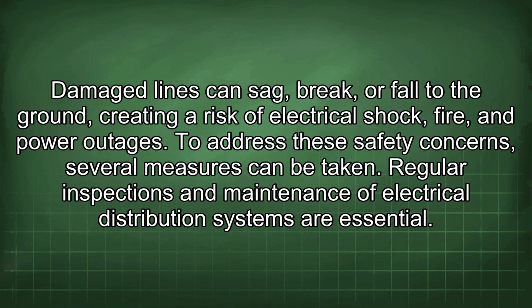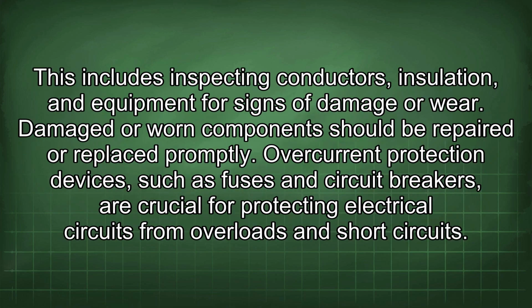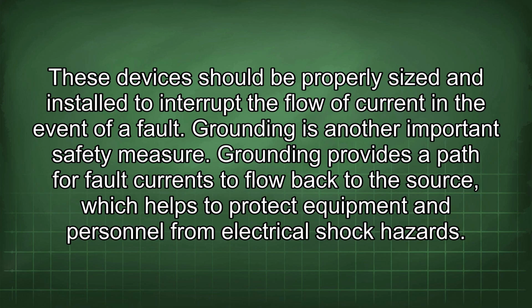Regular inspections and maintenance of electrical distribution systems are essential. This includes inspecting conductors, insulation, and equipment for signs of damage or wear. Damaged or worn components should be repaired or replaced promptly. Overcurrent protection devices, such as fuses and circuit breakers, are crucial for protecting electrical circuits from overloads and short circuits. These devices should be properly sized and installed to interrupt the flow of current in the event of a fault.